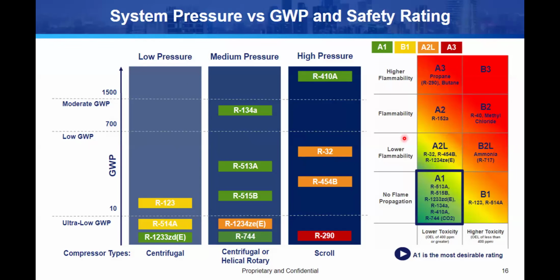Over here on the right-hand side, you see this box with the 8 little boxes in it. We've had this chart forever. This comes from ASHRAE Standard 34, which defines all the refrigerants. ASHRAE are the people that assign those R numbers. They're the ones that tell you, you get to be 410, you get to be 454. They assign those numbers to you based on your chemical compound, and a bunch of other stuff that comes up too. But in any case, they've had the standard for decades and decades and decades.